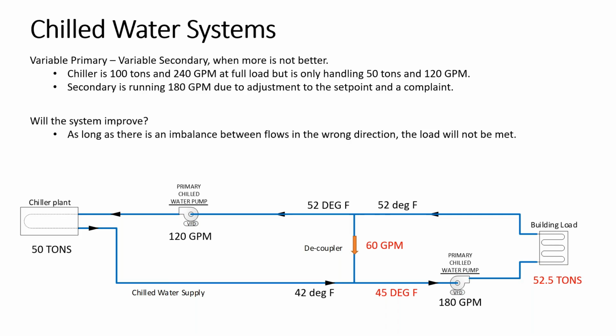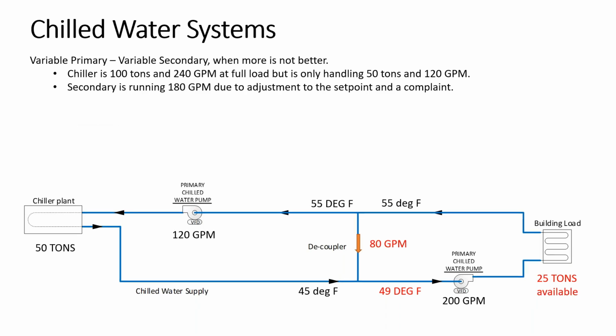Will it improve if you keep running it like this? If you keep going with this imbalance between the two flows, your load will get worse. You're putting 45-degree water out. Let's say you go up to 200 GPM, because after all, the valves are opening up on the load. You're just not getting the cooling you need because you're running 45-degree water instead of 42. So you're going to increase the flow, but nothing's changed on the chiller. It's still running at a 10-degree differential.